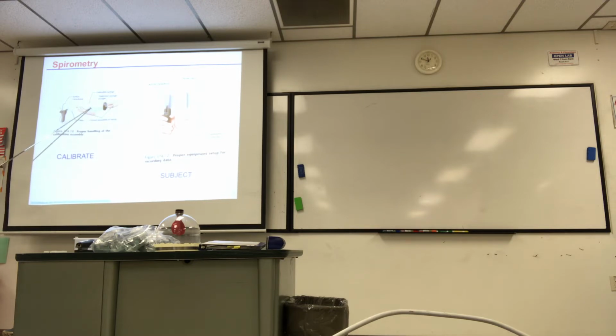The most important part of the equipment is actually this, the airflow transducer. There's a diaphragm in there. It can monitor how much air flows past it, okay? And it sends a signal to the computer, and you can see it on the screen. This is just pumping a syringe that simulates airflow.